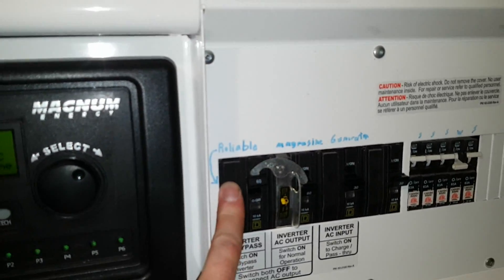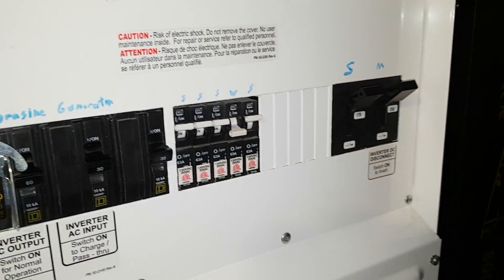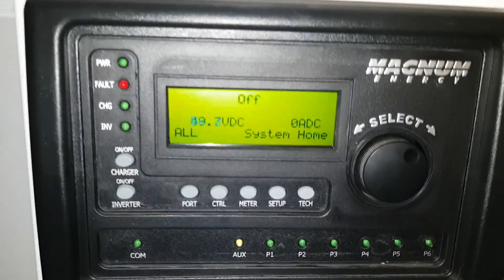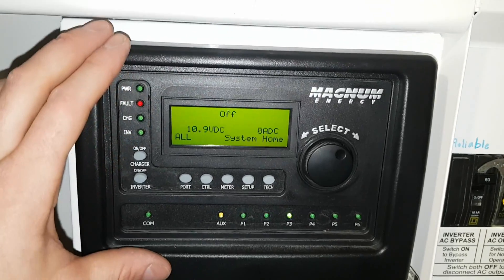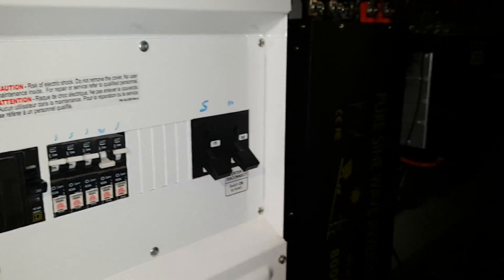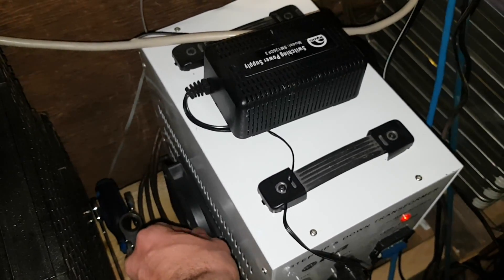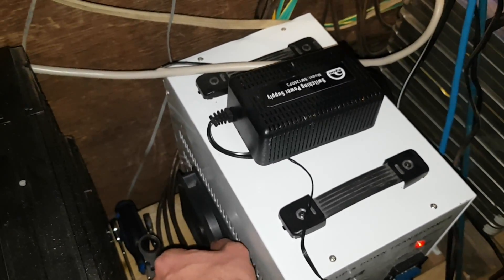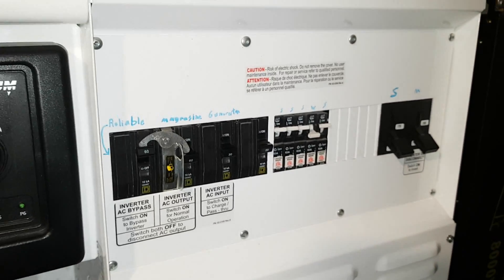As you can see we're now running on the Reliable inverter — the Magnum is completely off. I should actually shut the main Magnum breaker off. We don't need it. It takes about 12 watts just to keep itself running. So we're running solely off the new Reliable 8,000 watt inverter through this 10,000 watt transformer. I've got a fan on the side to help keep the transformer cool, because it does get quite warm under large loads.